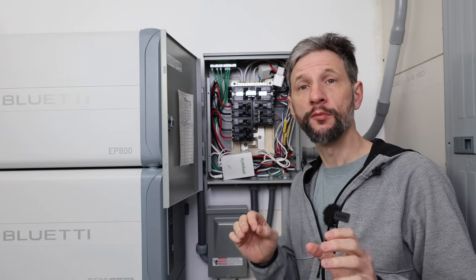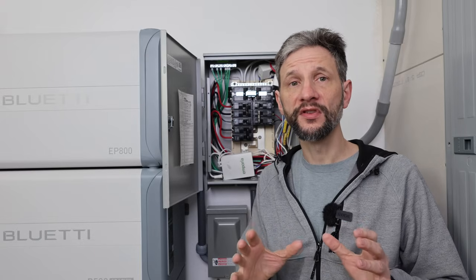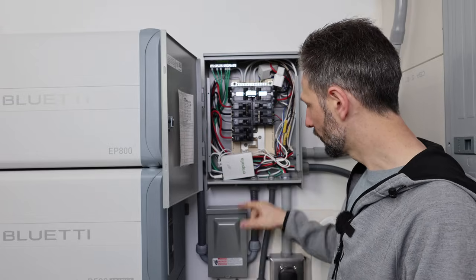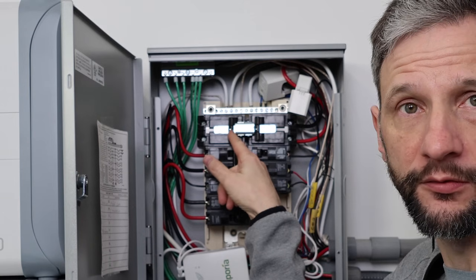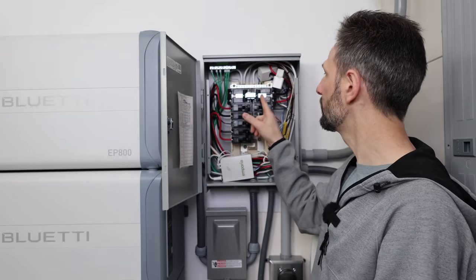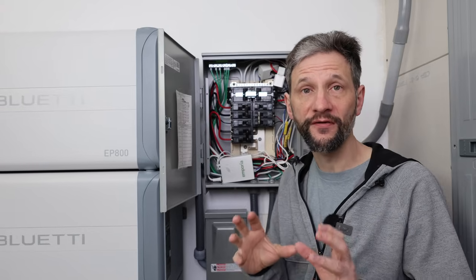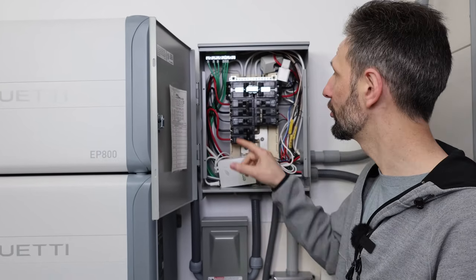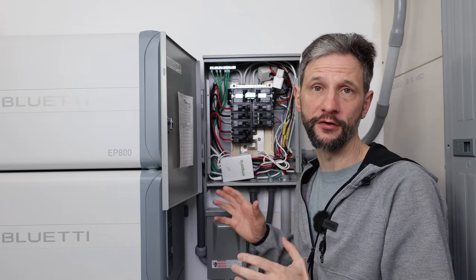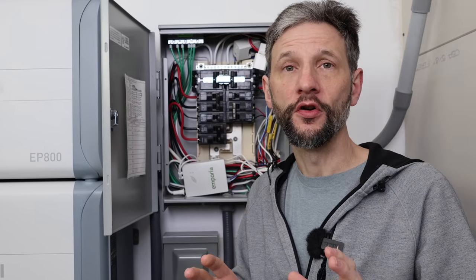There's one more AC connection that Bluetti recommends — a 50 amp grid connection to the other side of this transfer switch. To do that, I would run another set of six gauge wires from an additional 50 amp breaker in my main panel, but instead of running it to the Bluetti through this disconnect, we would run it directly to the other side of the transfer switch input. That way, if you ever need to bypass the EP800 for service, you'll still be able to power all the circuits in this panel by simply switching the transfer switch from the Bluetti input to the grid input. I plan to add an additional generator input that will connect to this grid input on the transfer switch instead.